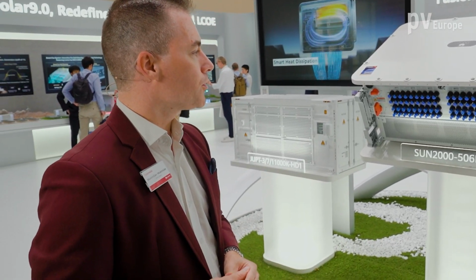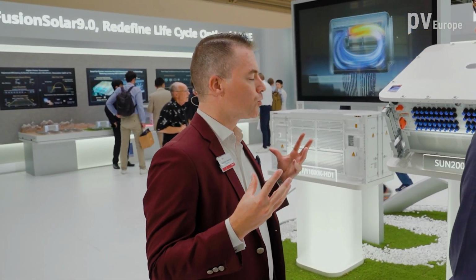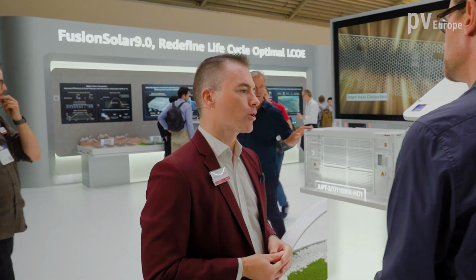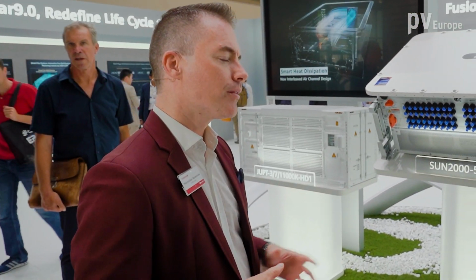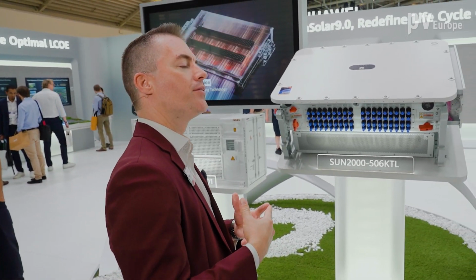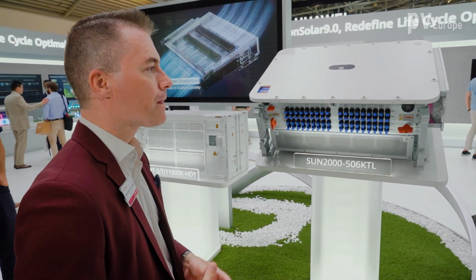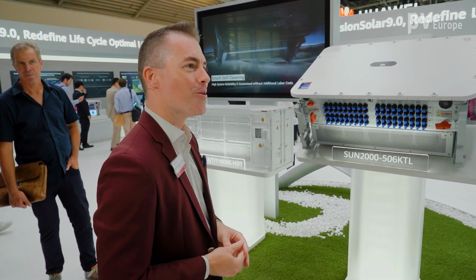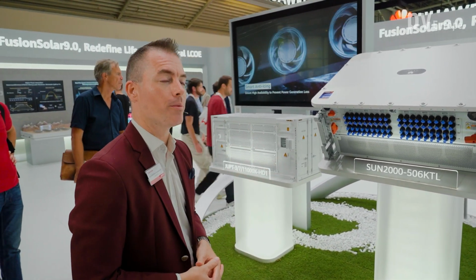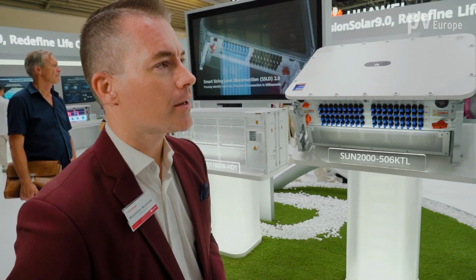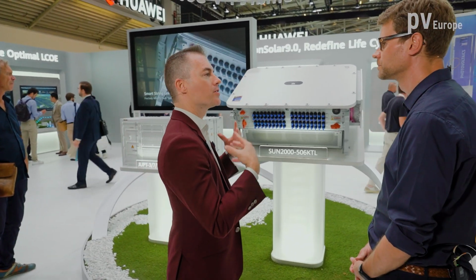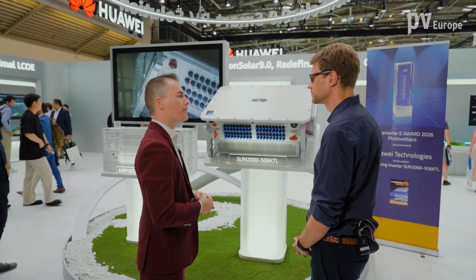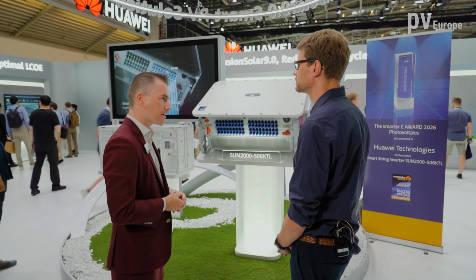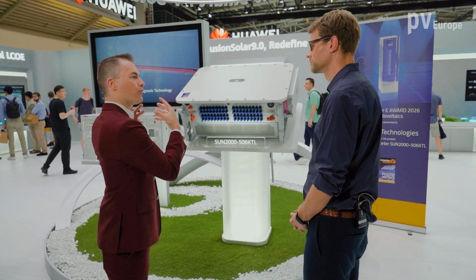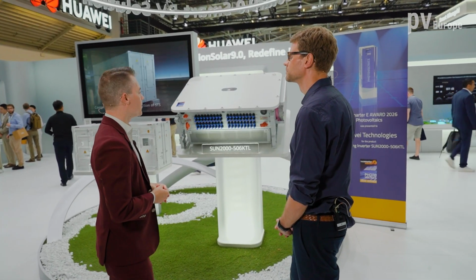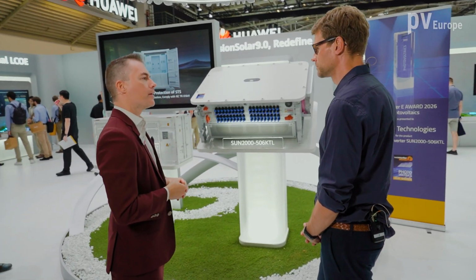Now, another very important thing is that if we look into the introduction of PV into the power grids, there has always been the criticism that more PV leads to a deteriorating grid, to lesser grid stability. That story is now finally over. We have introduced grid forming technology. This PV inverter is black start capable, can support inertia, can support grid forming, and therefore whatever happens in your grid, it can counteract on this. So we are bringing out the first real grid-friendly inverter in the string inverter production line here to the market.